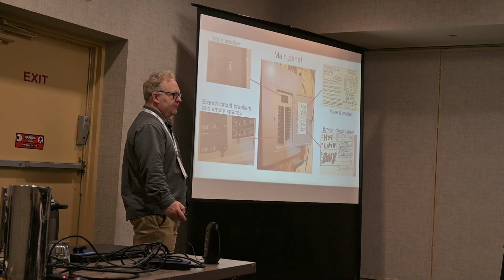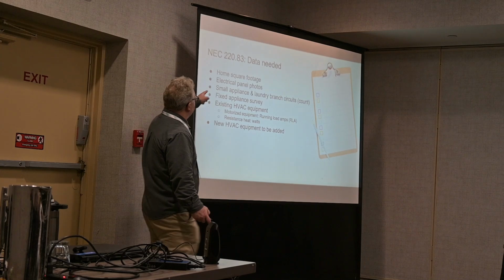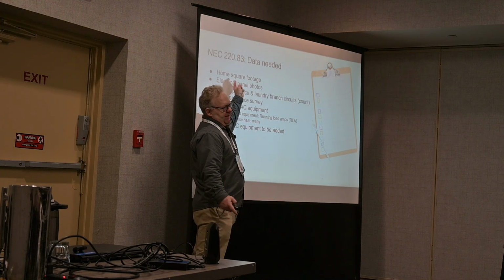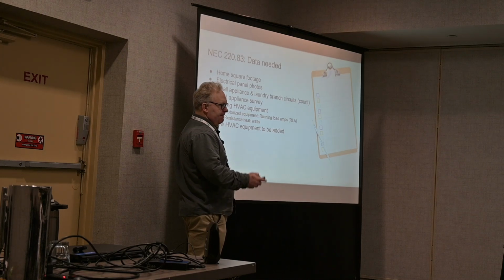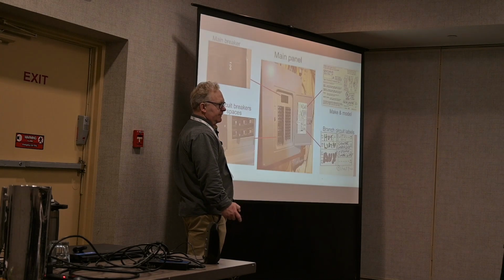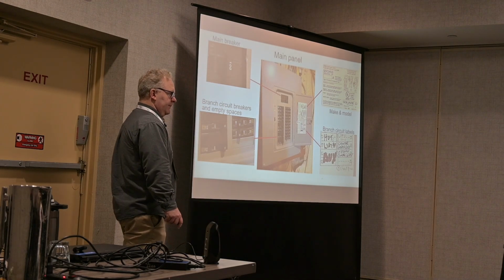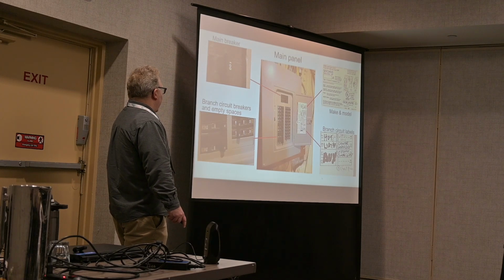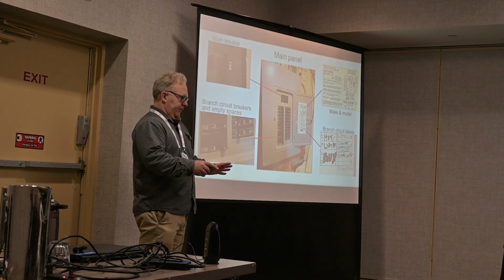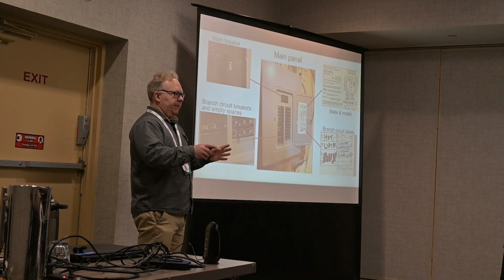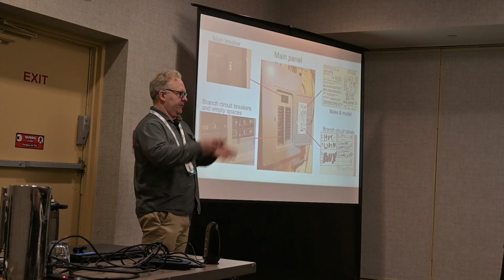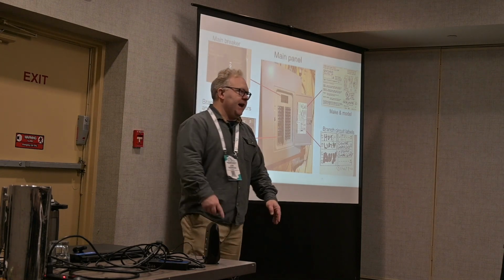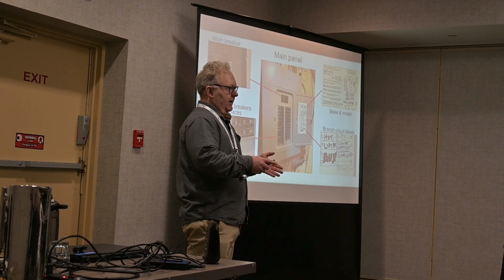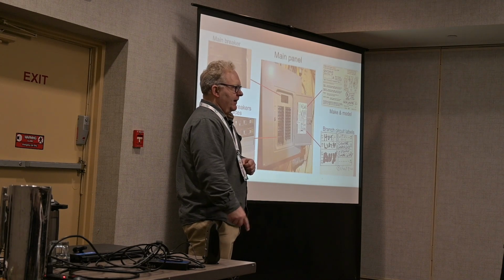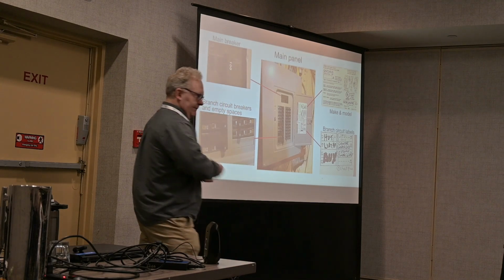Where does the existing service drop come into play into that checklist? So this is what I count under the electrical panel photos. Does a 100 amp panel automatically denote that it can't be upgraded to 200 amp without a service drop change? I would say that's not universal, but sometimes we have 200 amp conductors coming into a 100 amp panel. So that's something to be aware of. I really think that call is one that I'm always going to want to defer to an electrician in that case. But yeah, there are different possibilities.